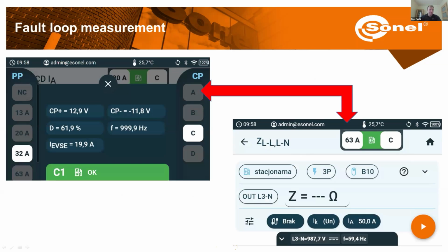So here, our meters from Sonel can perform such a measurement. First we need to remember to put the charging station in a certain condition, because we perform this measurement on live circuits. So the station needs to be in charging mode. It needs to be charging at the moment. And then the meter can perform the measurement. Also, once we put the type of the breakers into the meter, it will automatically evaluate the result after the measurement.